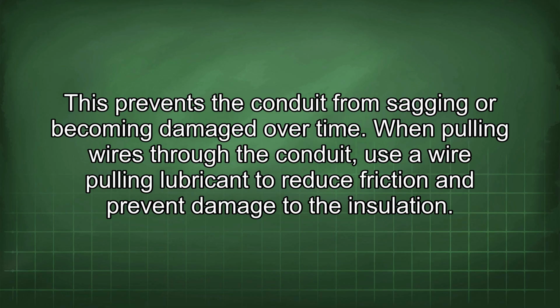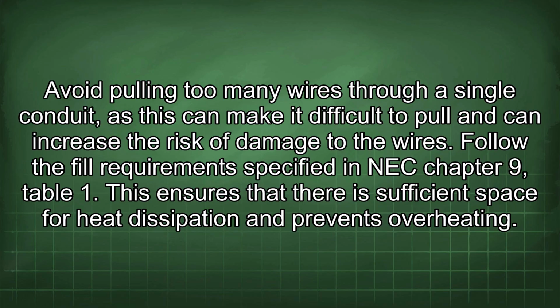When pulling wires through the conduit, use a wire pulling lubricant to reduce friction and prevent damage to the insulation. Avoid pulling too many wires through a single conduit, as this can make it difficult to pull and can increase the risk of damage to the wires. Follow the fill requirements specified in NEC Chapter 9, Table 1. This ensures that there is sufficient space for heat dissipation and prevents overheating.